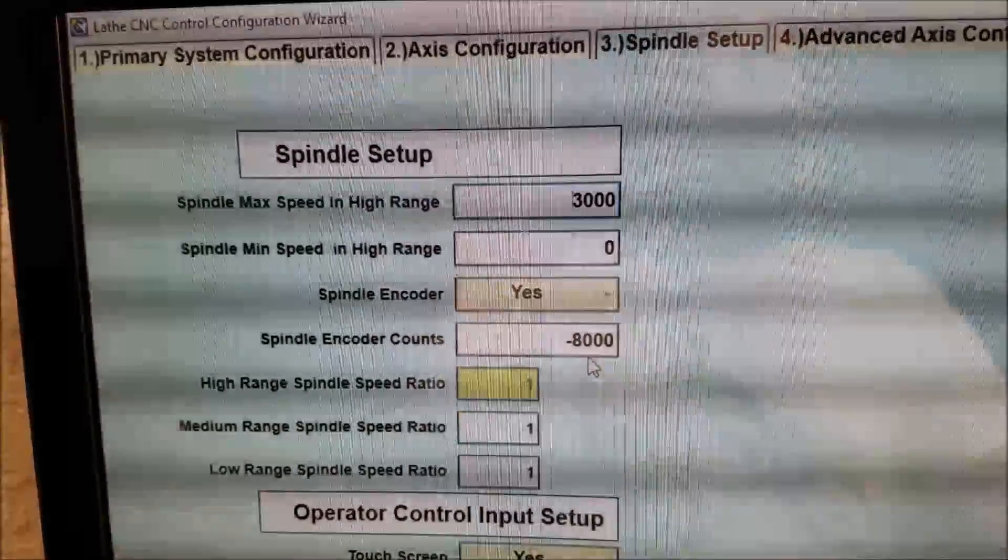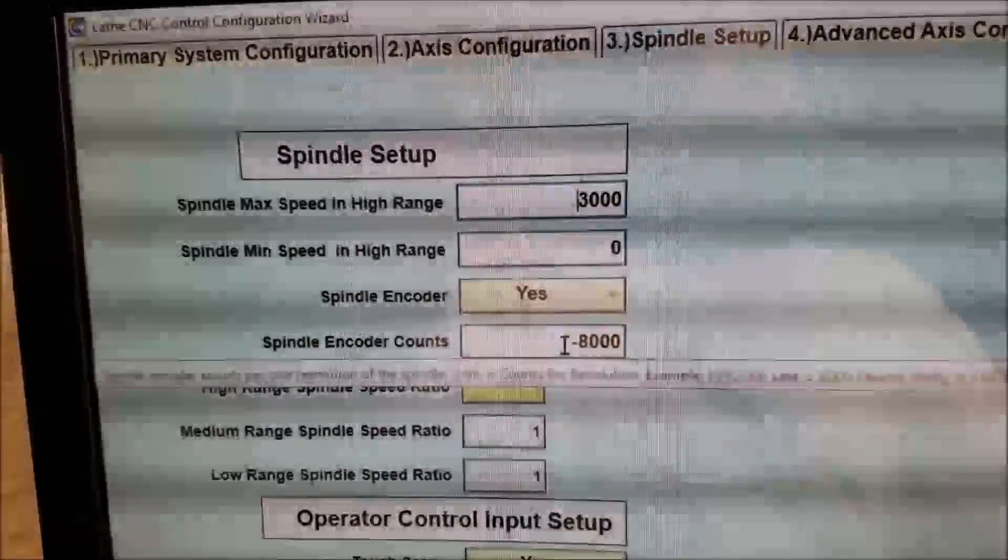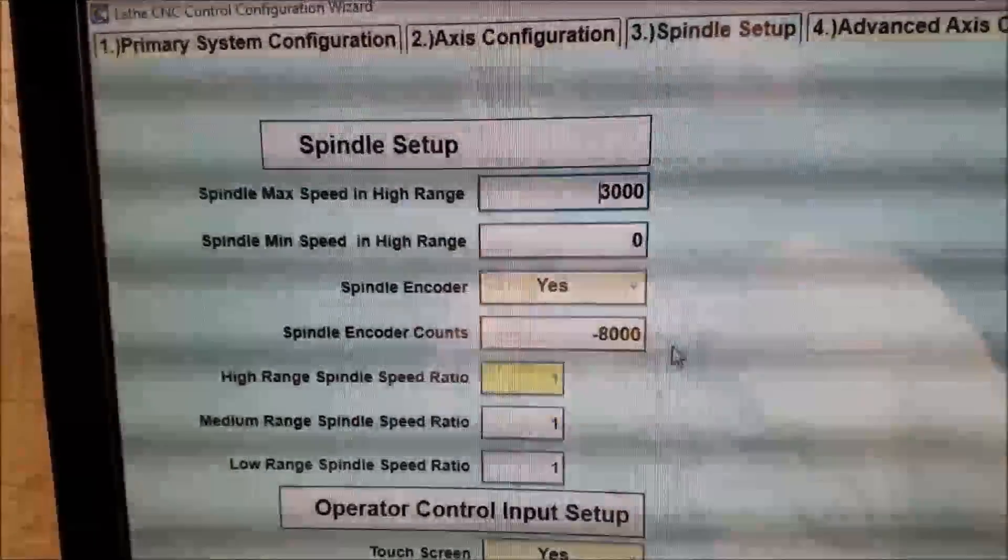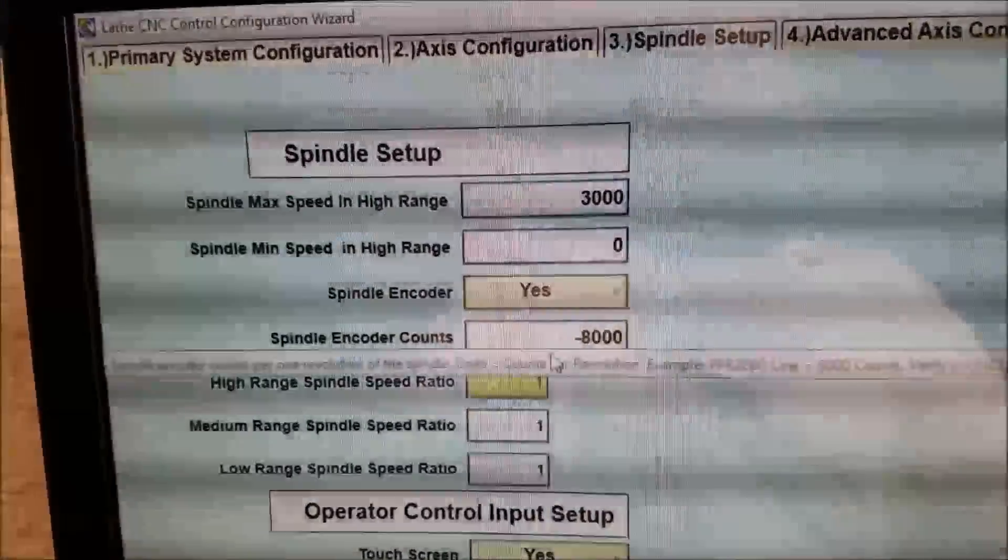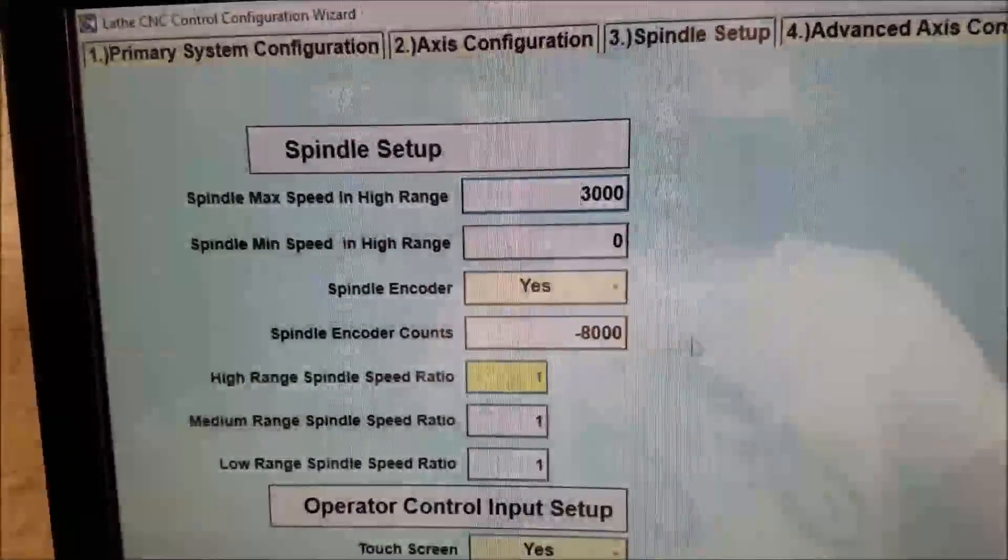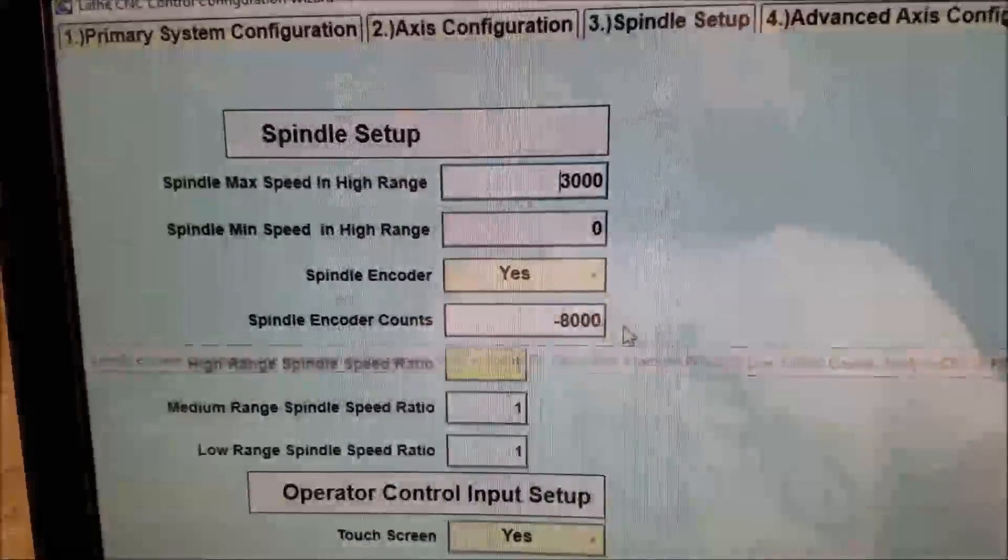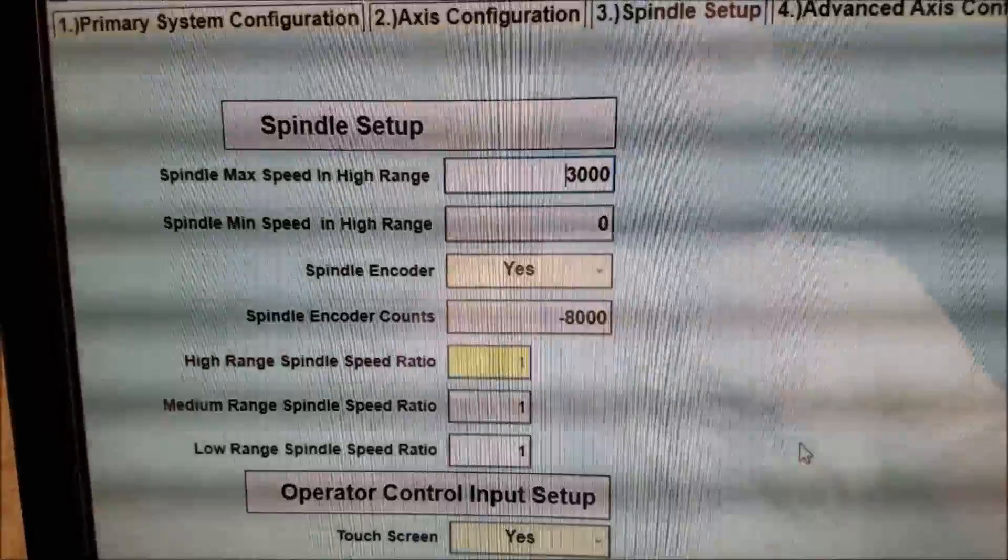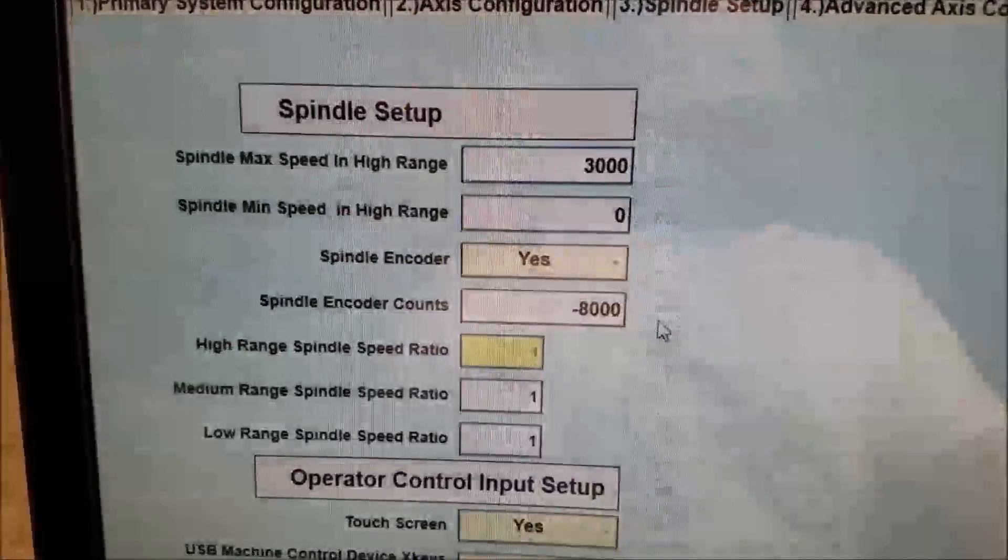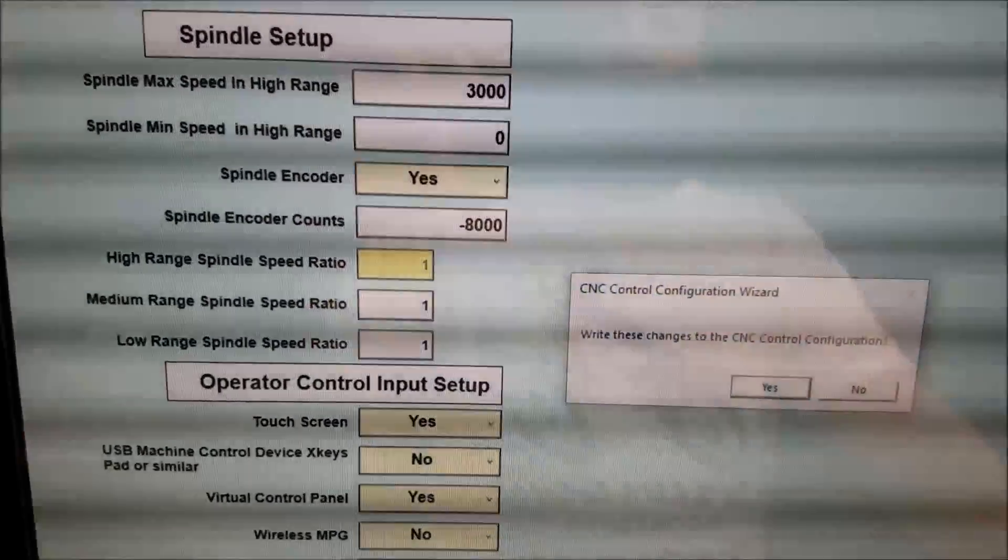And then, in my case, I'm going to start with negative 8000. It's either going to be 8000 or negative 8000. If you find you're getting your RPM readings the opposite of what you expect they should be, put a negative sign in it. So I'm going to start with negative 8000, but that's what I need. If that doesn't work, I'll make it positive 8000. And that's it—yes, I have a spindle encoder, and there's the counts per rev. And you write those settings.